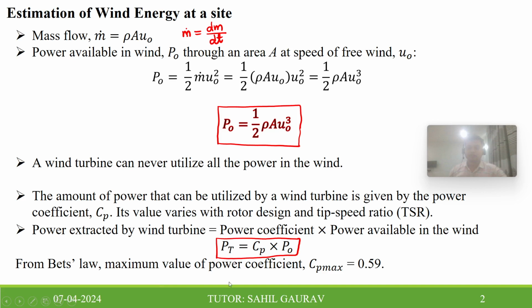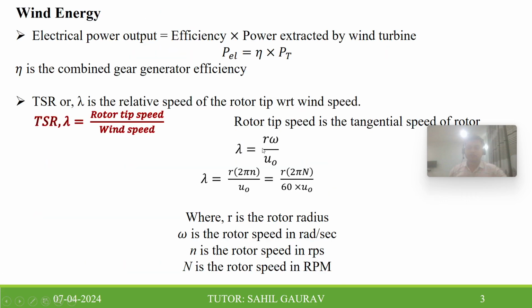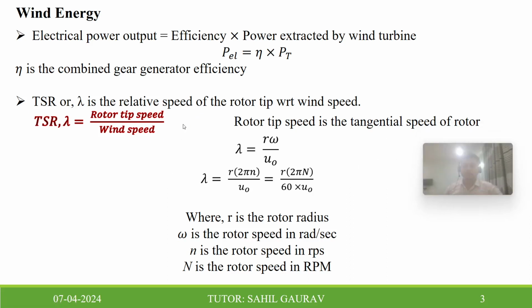Now from Betz's law, you can get the maximum value of the power coefficient as 0.59. And to calculate the electrical power output from this wind generation, that is the whole gear, generator and wind turbine, you have to multiply by the efficiency of the complete system, the efficiency of the combined gear and generator. So the electrical power output is equal to the efficiency multiplied by the power extracted by the wind turbine.